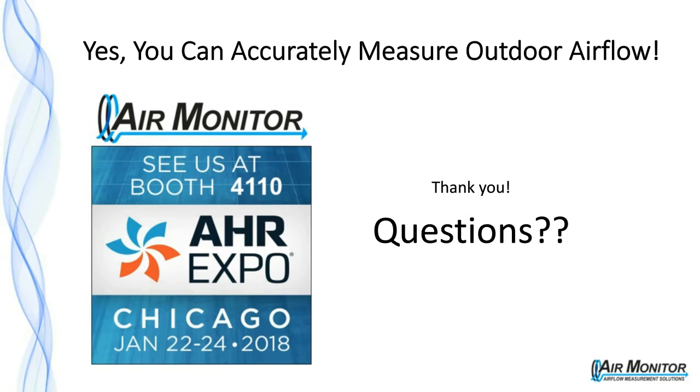So one of the claims to fame of a major competitor is that it remains accurate for many years before needing recalibration. How often does the static differential pressure system require recalibration? So for our system, the critical calibration point is the 0 point. And the system actually has an auto zero function, so it periodically zeroes the system. So there's no need to ever calibrate 0. As far as the span, or the maximum differential pressure for the system, it would be recommended to repeat the calibration about every 3 years.